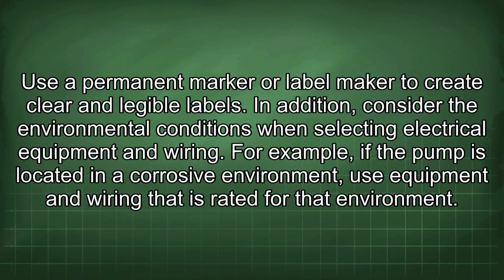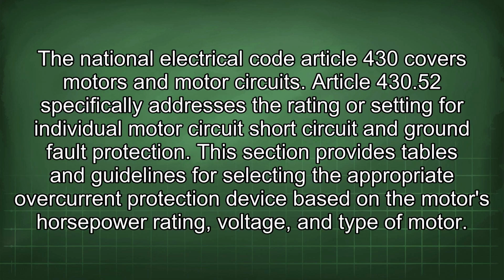In addition, consider the environmental conditions when selecting electrical equipment and wiring. For example, if the pump is located in a corrosive environment, use equipment and wiring that is rated for that environment. The National Electrical Code Article 430 covers motors and motor circuits. Article 430.52 specifically addresses the rating or setting for individual motor circuit short circuit and ground fault protection.